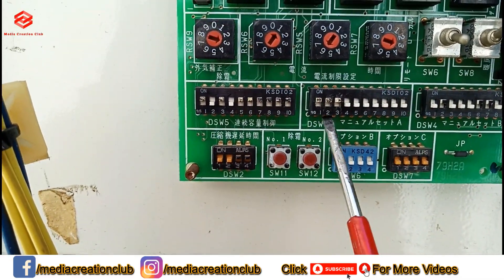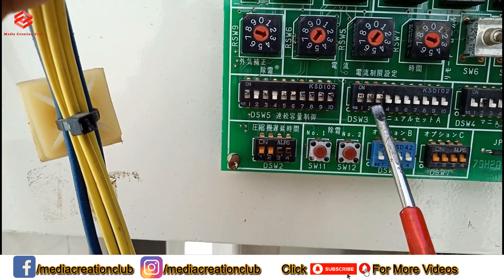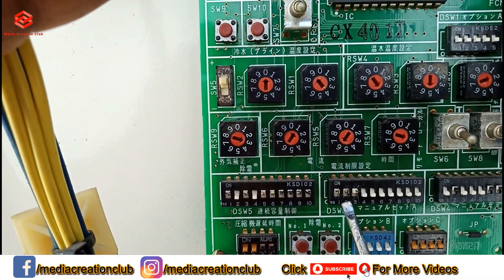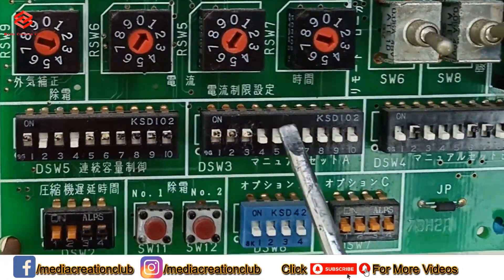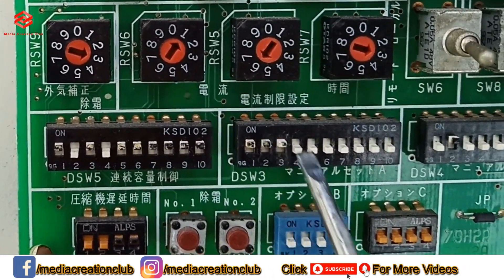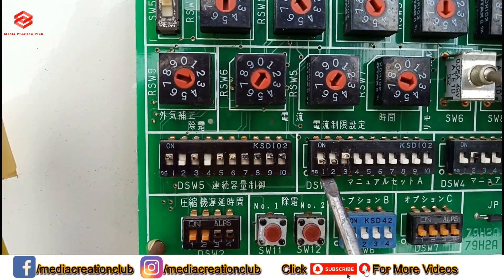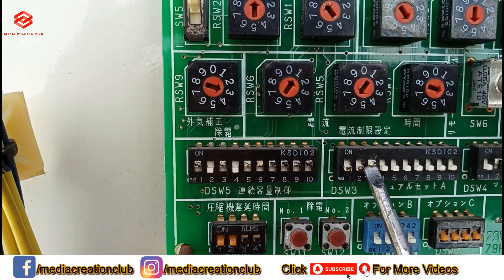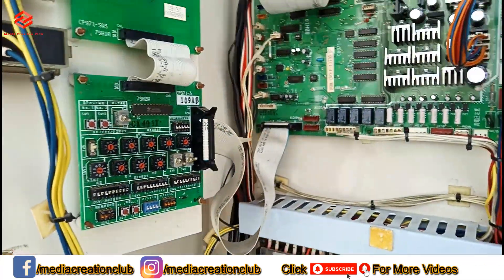This section here is for the compressors. In our chiller system we have three compressors, so we can choose which compressor to turn off to save electric cost. We can set how many compressors we need on. We can change this — I turn off number two, I turn off number one. So with those two compressors off and the chiller running on just one compressor, we can save a lot on electric cost. Let's turn it on now.